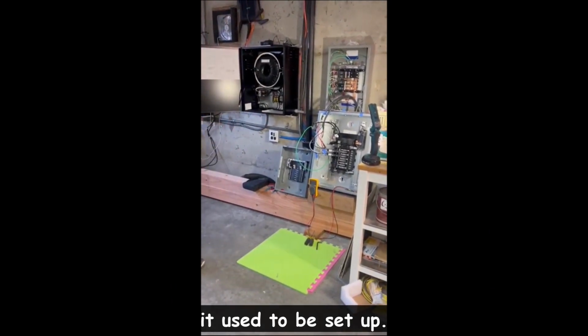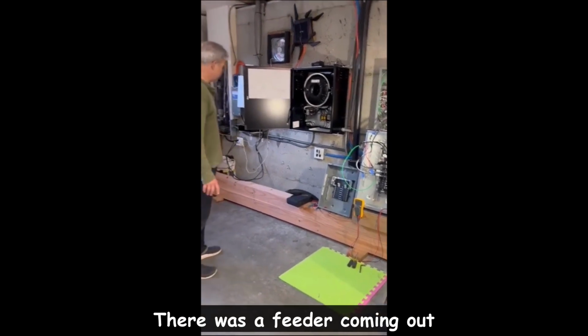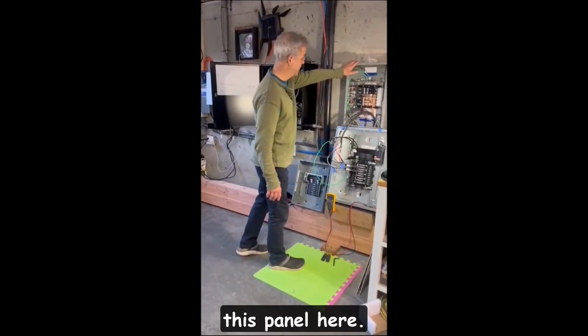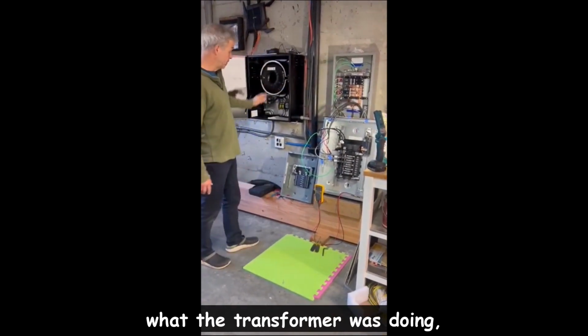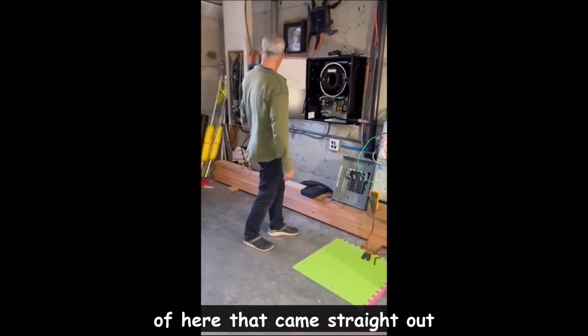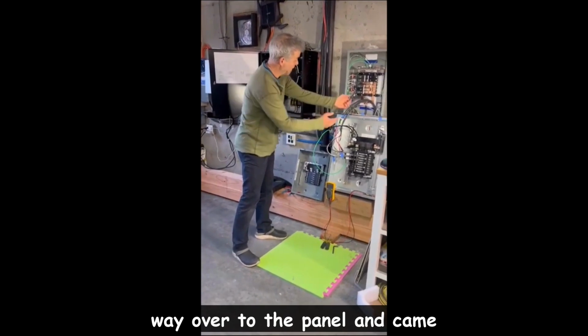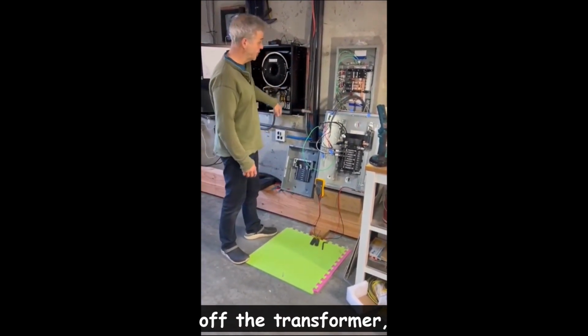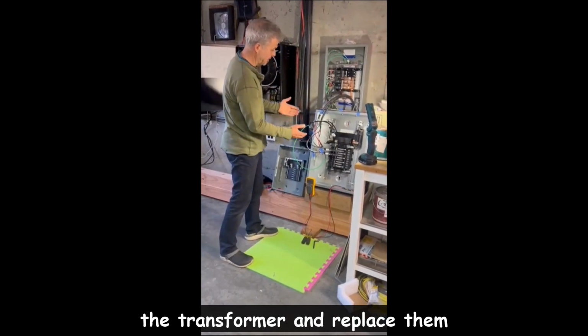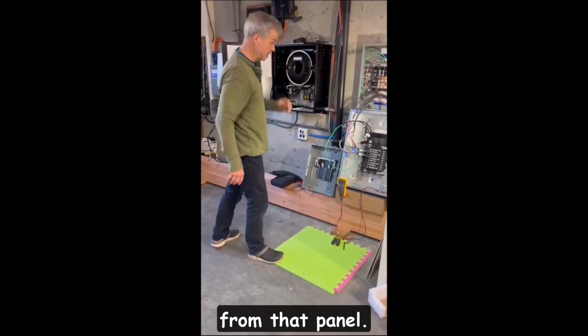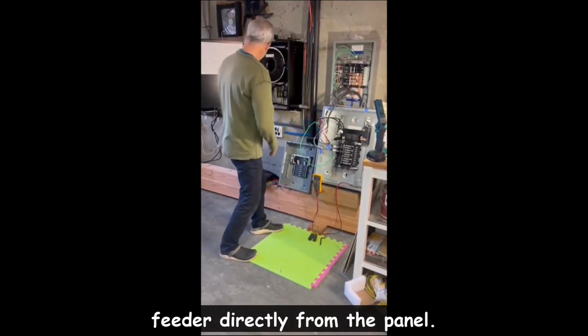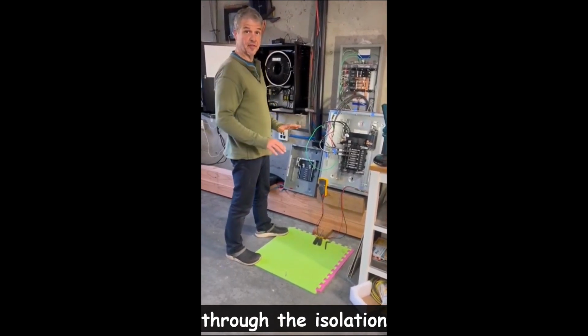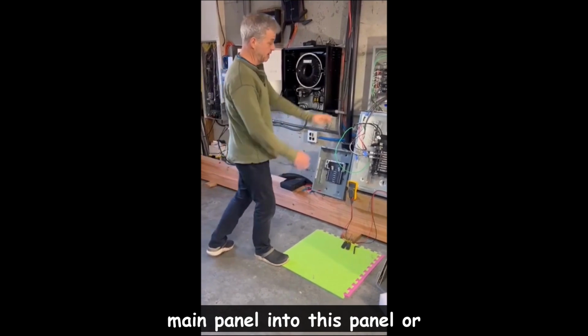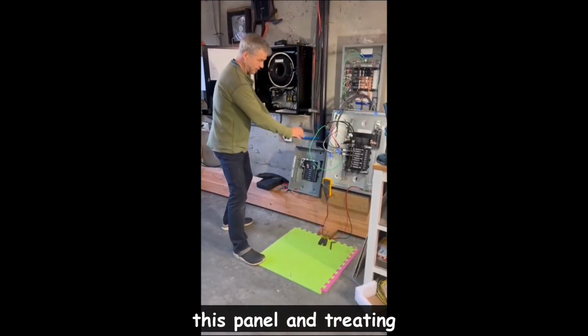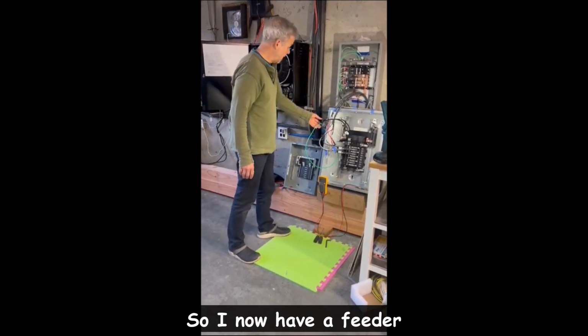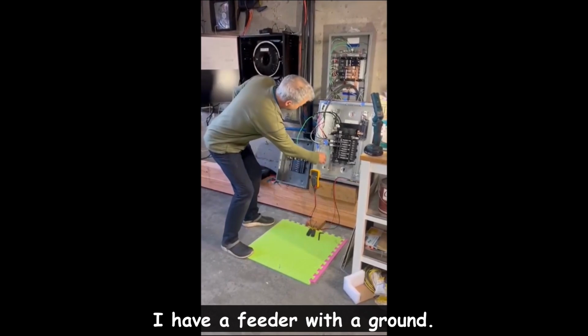To go over how it used to be set up: there was a feeder coming out of here that went into my transformer and fed into this panel. To really understand what the transformer was doing, I had another feeder coming straight out of the panel, routed over, and coming directly into the panel. So I was able to turn off the transformer, take the feeder wires off from it, and replace them with feeders directly from that panel. I've now pulled that feeder directly from the panel, so it's no longer going through the isolation transformer—it's just directly from my main panel into this panel, or into this panel, treating them as sub panels. So I now have a feeder with a neutral, a feeder with a phase, and a feeder with a ground.